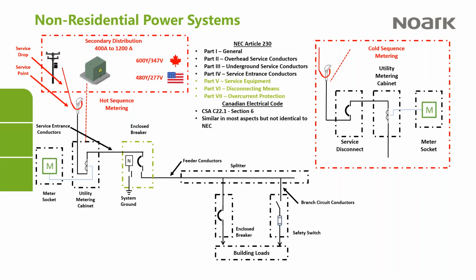Yeah. So the standards for enclosed breakers, in fact, for most enclosed products, including switchboards and motor control centers, there's something called the wire bending space. And this is driven by the UL and CSA standards. It means that you have to provide a certain amount of space between the terminals of the breaker and the side of the enclosure, and the amount of that space is driven by the size of the cables that are coming into it.